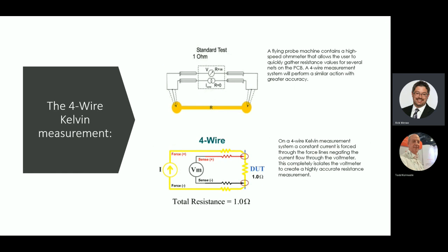Now, Todd, let's talk about what happens with four wire. As Todd mentioned before, we know that with four wires, it makes the lead resistance redundant. So what's important here is that when you have a red lead and a black lead, you still have it, but you have two reds and two blacks going across your device. Now what happens here is when the two red leads touch the copper material very close to one another, within a few microns, or depending on what kind of probe setup you have. If you're doing it manually, with manual probes, maybe you have 10 thou, 15 thou in between. But when you're using automatic testers, the probe tips are within microns apart. So you're basically touching the device that you're wanting to measure at the same spot within, let's say, 20 or 30 microns.